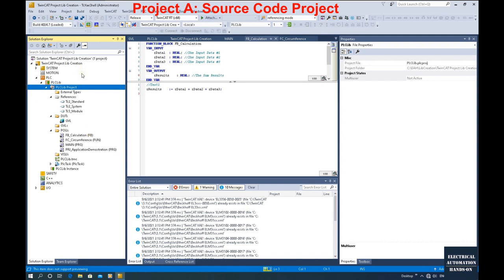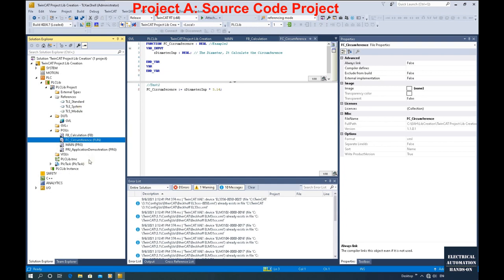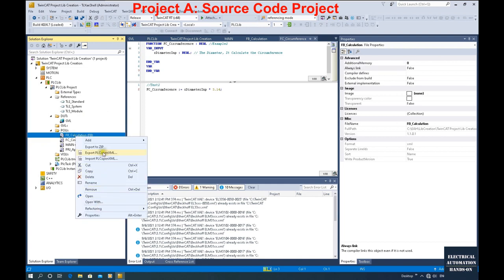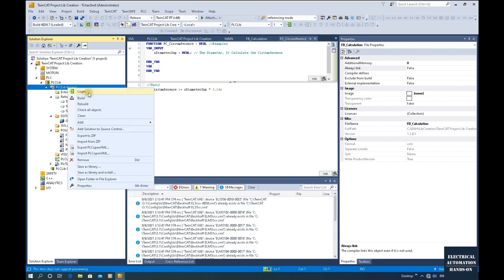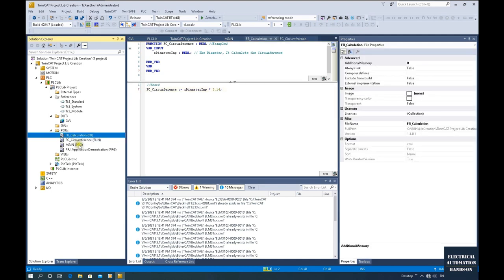I highly recommend you create one specific project, and under this project only include the core function blocks or functions. That's because when we export this project as a library, it will export the entire PLC project — it cannot export individual function blocks or functions. So you better prepare one specific PLC project dedicated to this library export. Everything within this project will be saved or exported as a library, so only include the important functions or function blocks you want to export.